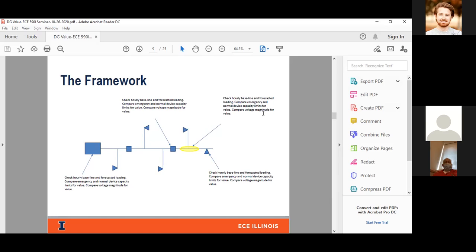These are things like the conductor itself, secondary distributions, transformers, reclosers, or regulators that are out on the line. And again, based on the framework that we just described, we're going to check the hourly baseline and forecasted loading, compare those with the planning criteria. These are the emergency and normal operating limits for each asset. We're also going to compare here voltage profiles against what, again, the planning criteria is, and assign value to DG that's downstream of that accordingly.